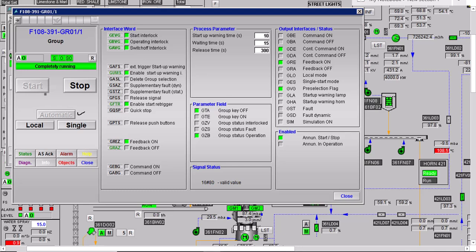The working of the block both in HMI and logic will be discussed in the coming video, but in this video I will discuss the input and output interfaces of the C Group block. On the HMI we can start and stop all equipments in the group in automatic mode. If we want to operate each device in local mode, we simply switch it to local mode. Local mode means the local start and local stop buttons become active and that device can be operated locally. Single mode means to individually operate that equipment from the faceplate HMI, while automatic means to operate all equipments simultaneously.